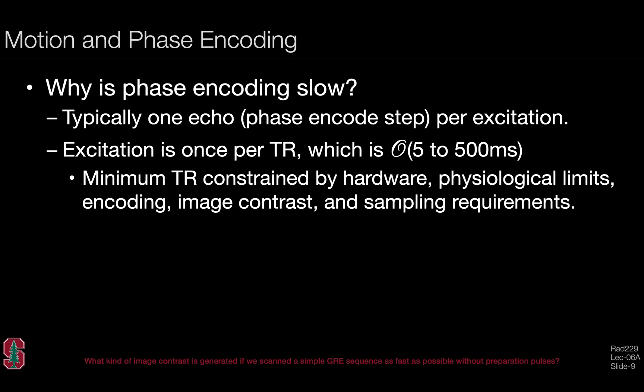Why is phase encoding slow? Typically one echo, that is one phase encode step, is acquired per excitation. The excitation only happens once per TR for a typical sequence, which is on the order of about five or even as long as 500 milliseconds. The minimum TR, that is how quickly we obtain individual echoes, is constrained by many things, including hardware, physiologic limits, encoding specifications, desired image contrast, and sampling requirements.